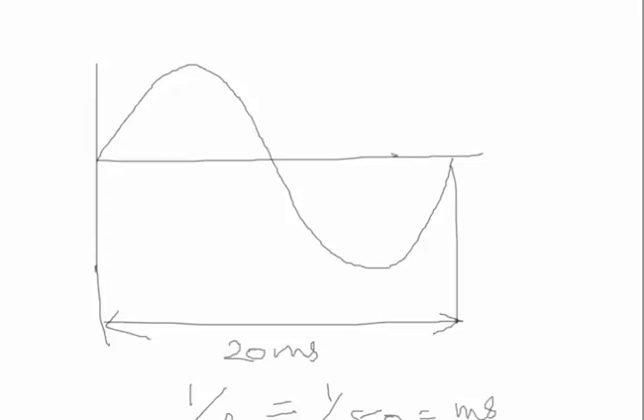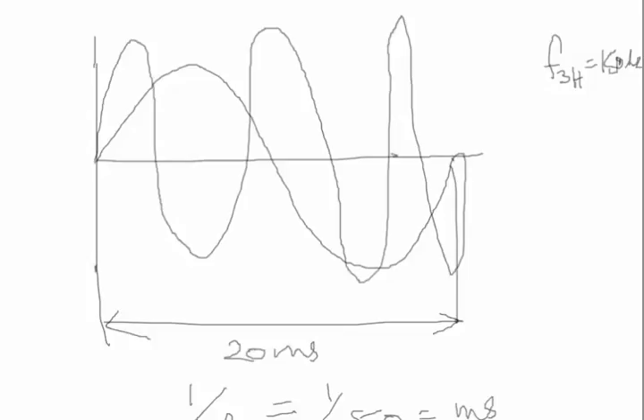Harmonics are multiples of fundamental frequencies introduced by loads such as switch mode power supplies or rectifiers or some other loads, your arc furnaces. So a third harmonic would be 150 Hertz, which means for one cycle of fundamental, there would be 3 cycles of the third harmonic. So you might have something like this. Forgive me for the sketch.